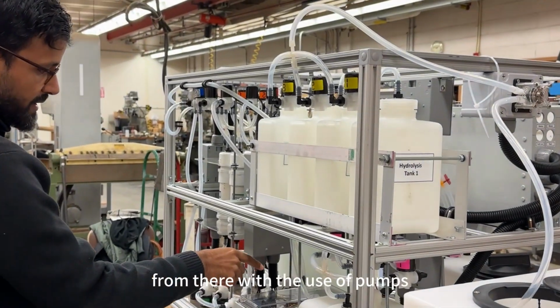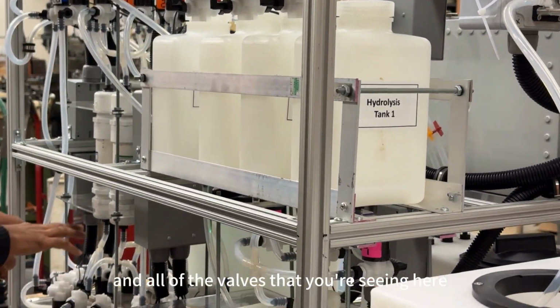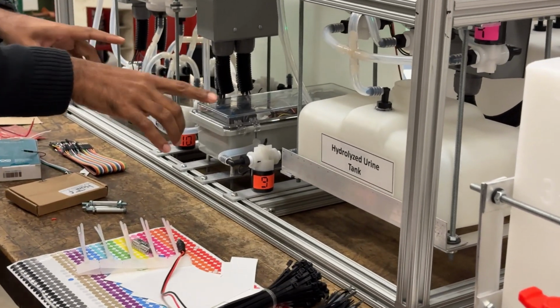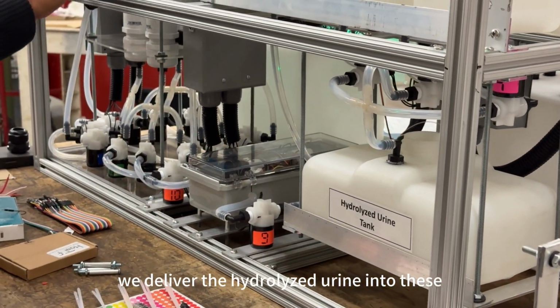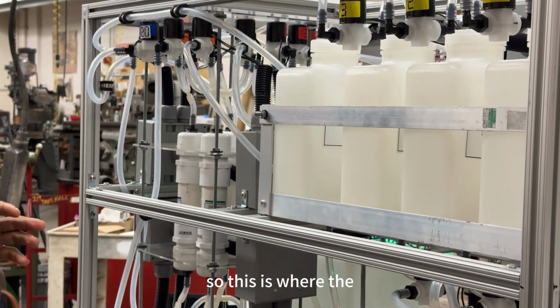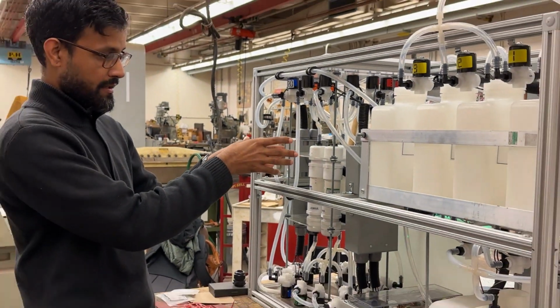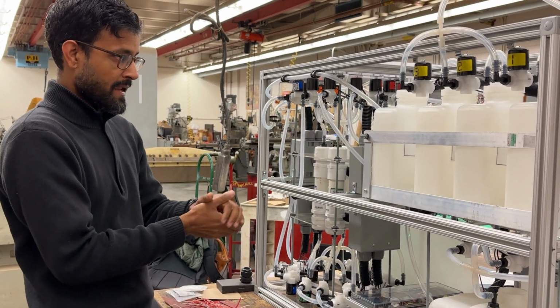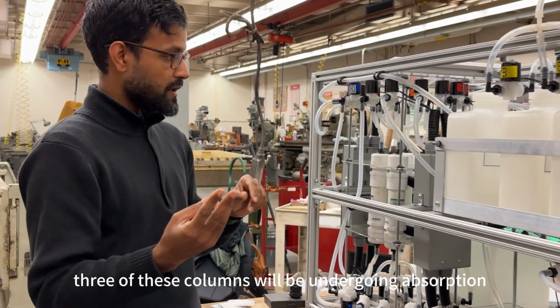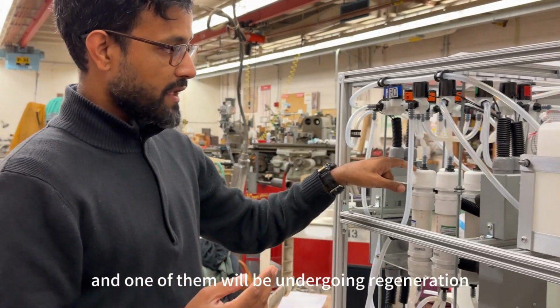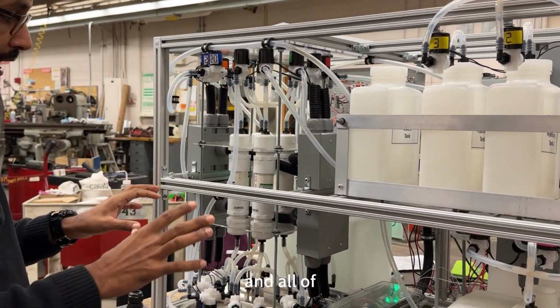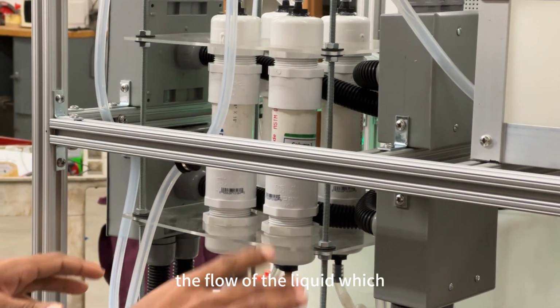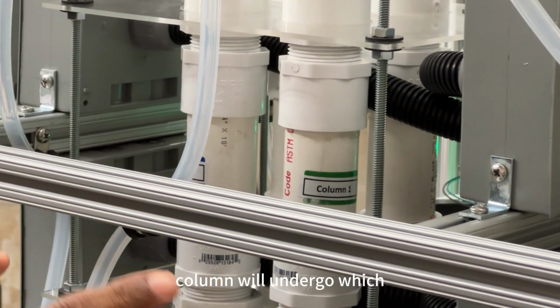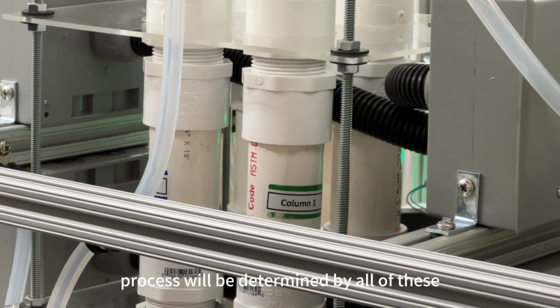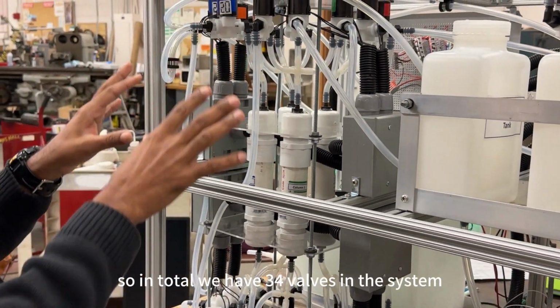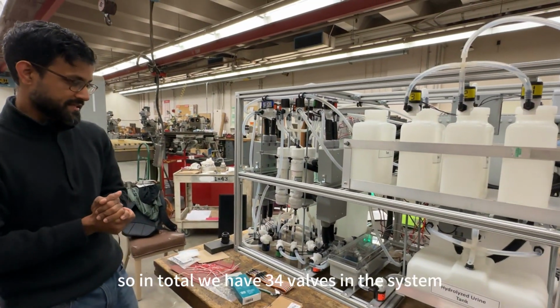Once the urine is hydrolyzed in these tanks, it's delivered to the hydrolyzed urine tank. From there, with the use of pumps and all of the valves that you're seeing here, we deliver the hydrolyzed urine into these ion exchange columns. This is where the ion exchange resin is packed into these columns. At a given time, 3 of these columns will be undergoing adsorption, and 1 of them will be undergoing regeneration. Which column will undergo which process is determined by all of these valves that you're seeing that are numbered. In total, we have 34 valves in the system.